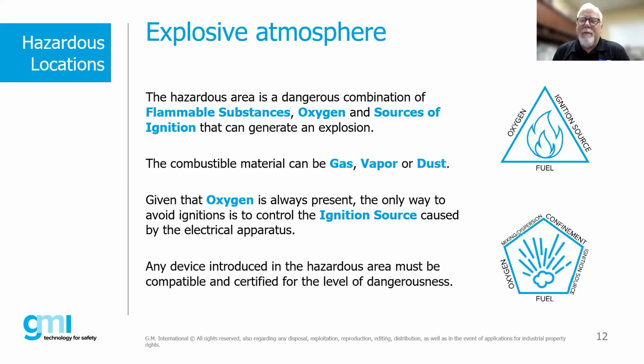So a little bit about explosive atmospheres. Just to get to the fundamentals, and this applies whether it's IS or flameproof or whatever protection concept they're using, any environment in which we could have more or less oxygen, fuel, and an ignition source is considered potentially a hazardous location. It could be a gas, vapor, or dust, and that's one thing many people don't necessarily think about, but dust hazards can certainly be very explosive. Grain elevators, coal mines, facilities like that, or even food processing, could be potentially hazardous locations. Given that oxygen is basically always present, the only way to avoid ignitions is to somehow control the ignition sources caused by electrical apparatus.